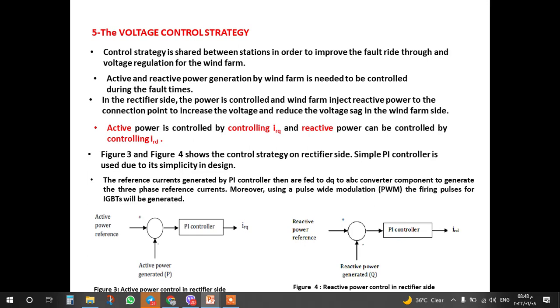Figure 3 and Figure 4 show the control strategy on rectifier side. A simple PI controller is used due to its simplicity in design. The reference current is generated by the PI controller, then the dq to abc converter components generate the three-phase reference current. Moreover, using pulse width modulation, the firing pulses for the IGBT will be generated.